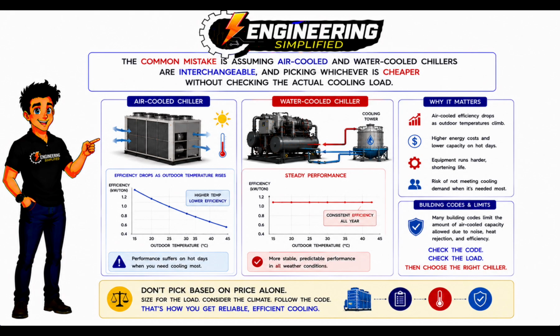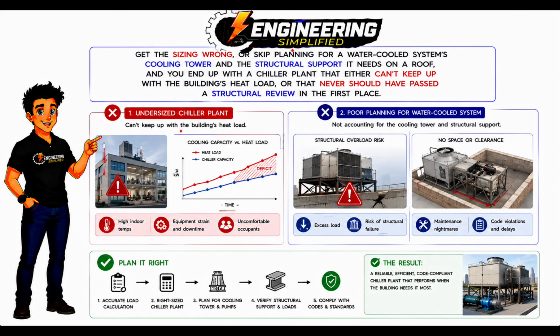The common mistake is assuming air-cooled and water-cooled chillers are interchangeable and picking whichever is cheaper without checking the actual cooling load. Air-cooled systems lose efficiency as outdoor temperatures climb, and many building codes cap how much air-cooled capacity is even allowed. Get that sizing wrong, or skip planning for a water-cooled system's cooling tower and the structural support it needs on a roof, and you end up with a chiller plant that either can't keep up with the building's heat load or that never should have passed a structural review in the first place.